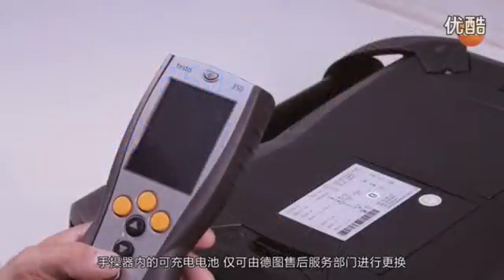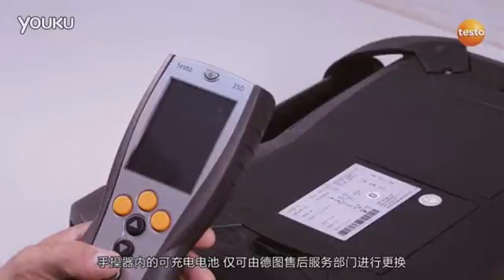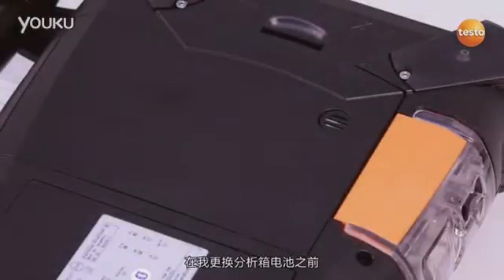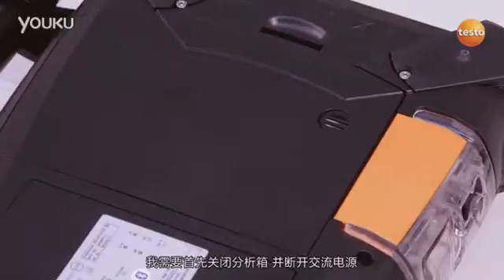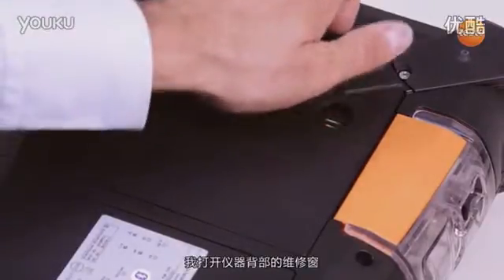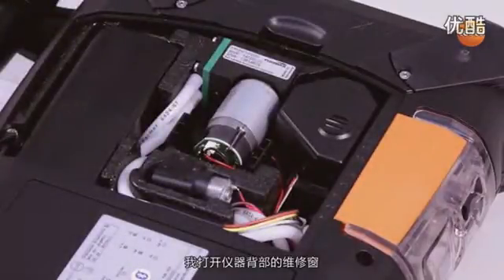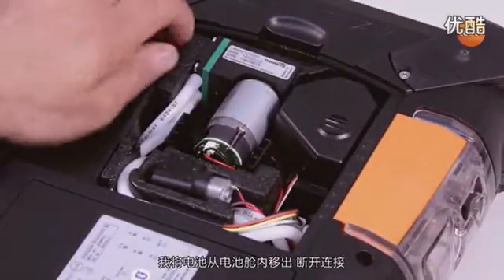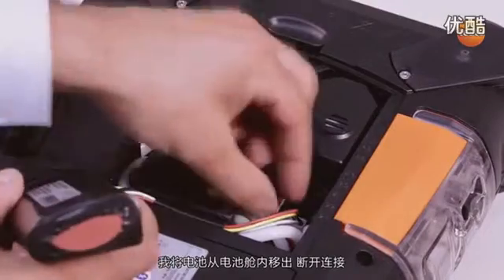The rechargeable battery in the control unit can only be changed by Testo customer service. Before I can replace the battery in the analyzer box, I have to switch off the analyzer box and disconnect it from the power grid. I open the service cover on the rear of the instrument. I remove the battery from the battery compartment and disconnect it.